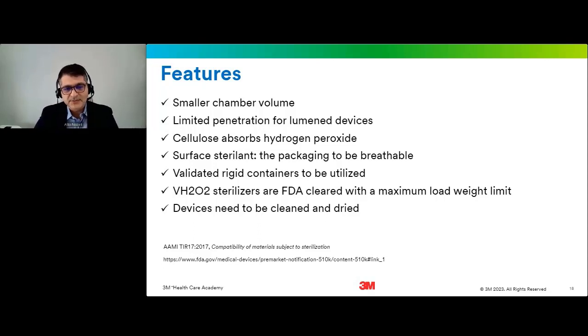We talked about the features, but now these are some of the limiting features. When I say limiting, it's in comparison. So, such as smaller chamber volume in comparison to steam. In steam sterilization, we have larger sterilizers with larger chambers, but we have smaller chambers in the vaporized hydrogen peroxide system. Limited penetration down long, narrow lumens. Again, when we say limited, it means in comparison. So lumen lengths and inner diameters that are FDA cleared and written in the manufacturer's instruction for use for that sterilizer should be used. The number of lumens is more than just working channels. So air channel, water jet channel, they're also channels.